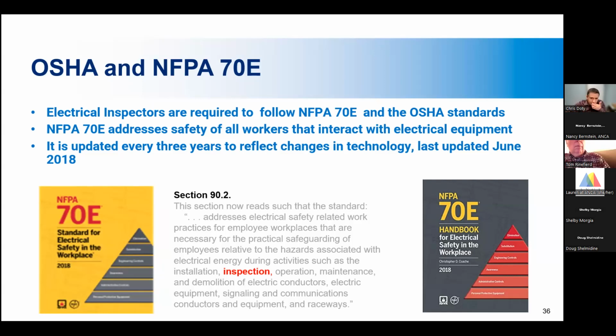To comply with this, you would do an initial risk assessment to make sure that you're aware of all the job site hazards that may be present. If your inspection involves removing covers to electrical equipment, the assessment will help you determine if PPE, or personal protective equipment, or other methods of mitigating those risks will be required. And it's important also to keep in mind that other job site hazards may be present. You may need fall protection or other PPE that isn't necessarily for electrical safety. So keep that in mind as you go through your risk assessment.